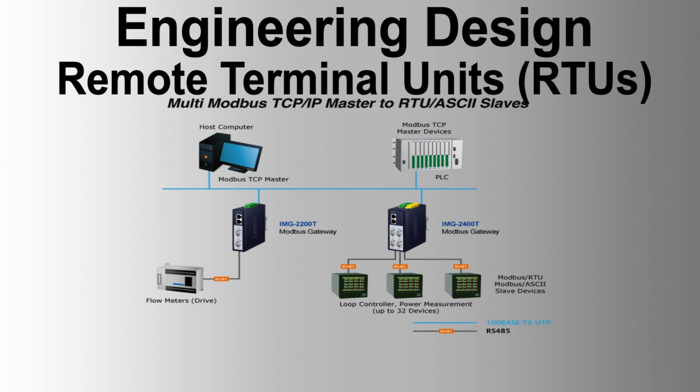3. Remote operations. RTUs allow for remote downloading of configurations, parameter changes, and application software. They also support remote diagnostic capabilities from central control rooms. 4. No single point of failure. The design ensures that no single component logic failure results in a false output operation. Failure of the first component, in conjunction with a second component failure that could cause a false command, must be detectable during normal RTU operation.